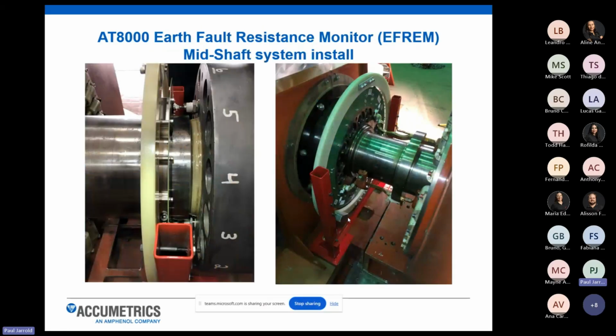Here's some more images of what that system looks like installed on a customer's machine. The image on the left shows you the rotating transmitter installed directly on the shaft. And then on the left side of that is the pickup antenna. So this would be in alignment. This would normally be moved over to the right and come into perfect alignment with the transmitter, and you can see that on the image on the right. We just wanted to show you for the image on the left what those two pieces look like installed on a customer's machine. And then the image on the right is what it would look like during final installation.